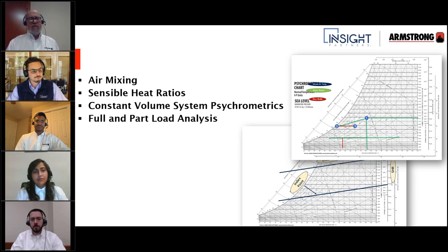The thing that I found, Tony, is yes, different manufacturers print them differently. I have 3 different ones sitting on my desk at home, and they all look a little bit different, but they all have the exact same information on it. If I plot the same state points, I get the same answers. I do have one at home that is a high temperature version, and it does look a little bit different because the temperature ranges. It doesn't go as low as a conventional psych chart. It starts about midpoint of a conventional psych chart like we've been using today, and goes to a much higher value. And that's for if I'm doing high temperature air systems or industrial process where I've got hot air that I'm dealing with, those things I have to deal with differently.